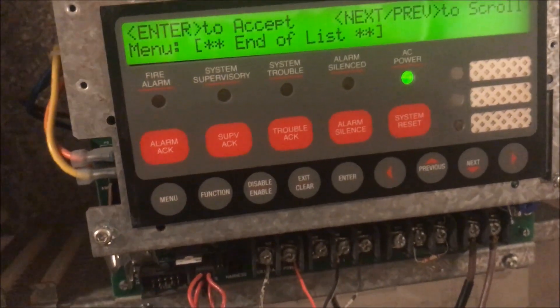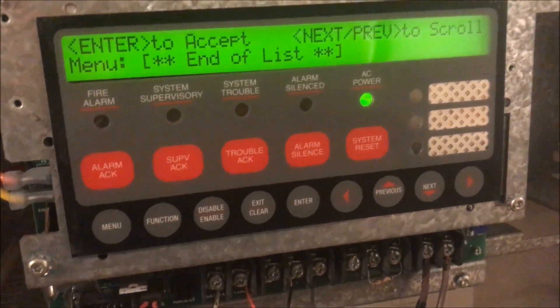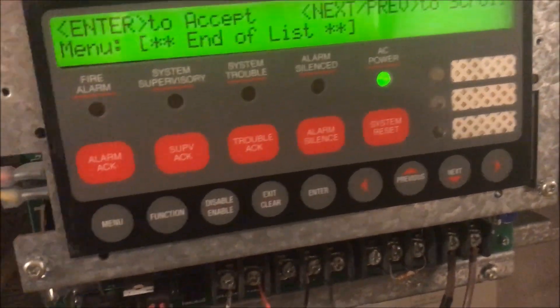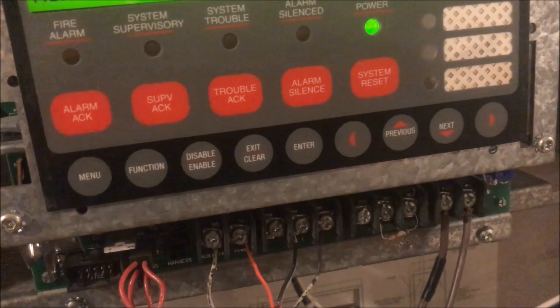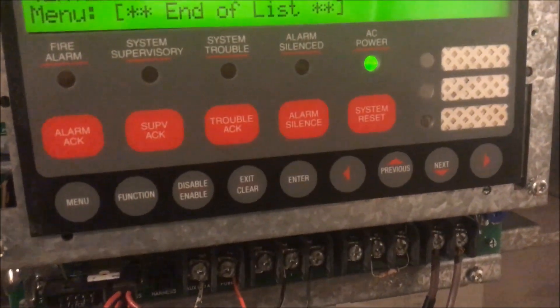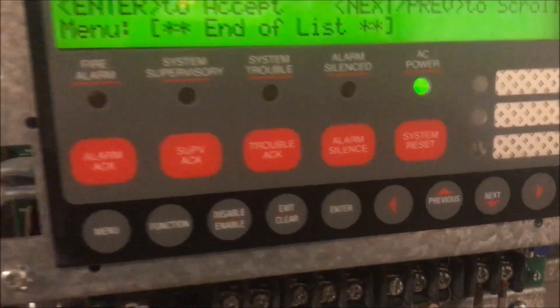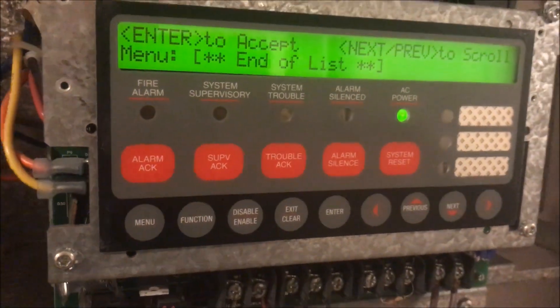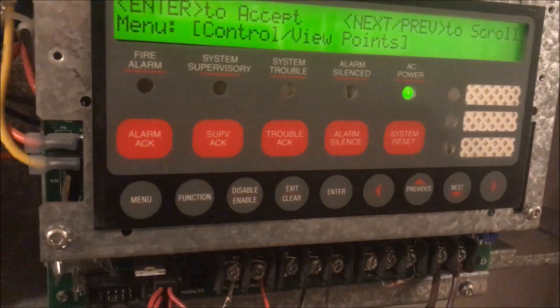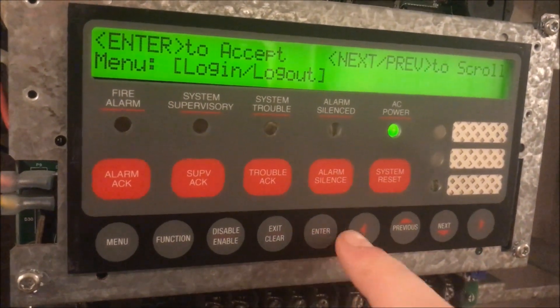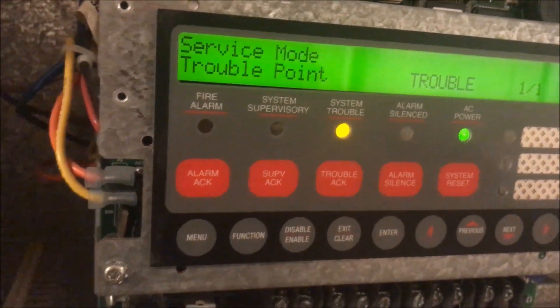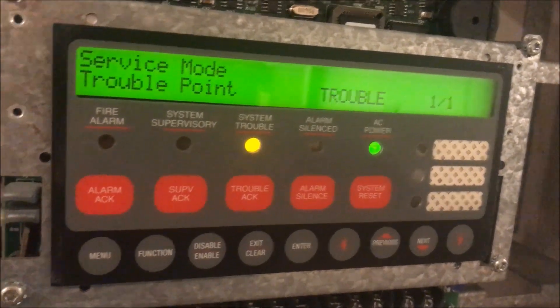Now jumping into level four briefly, because someone requested how to add a point. I touched on it in my setting an IDNet address point video for the Simplex 4010, but didn't go too in depth. From any login level, go to Menu then Login and log in to level four — and then you'll get a service mode trouble, because at this level someone has complete access to your panel, and that gets sent to the central station.